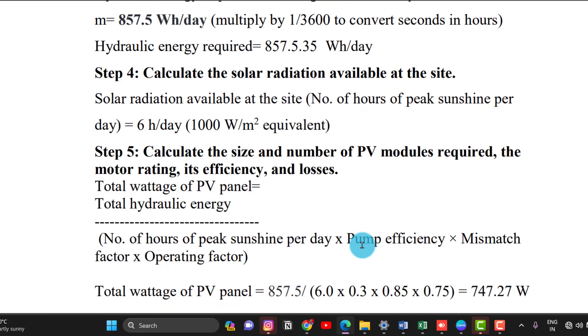Step 5: Calculate the size and number of panels. Total wattage of PV panels equals total hydraulic energy divided by (peak sunshine hours × pump efficiency × mismatch factor × operating factor): 857 ÷ (6 × 0.30 × 0.85 × 0.75) ≈ 747 watts. Number of panels equals 747 ÷ 75 Watt peak ≈ 10 panels.